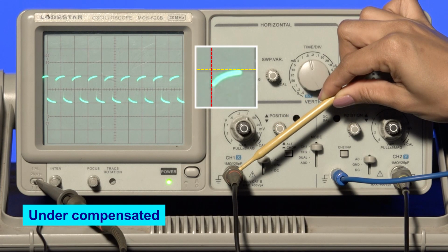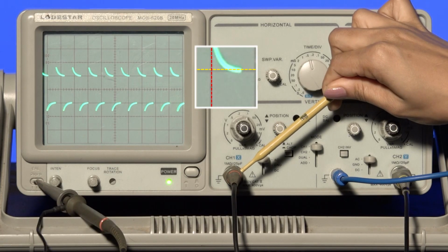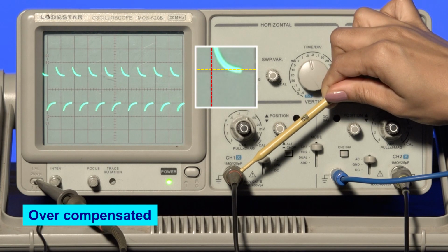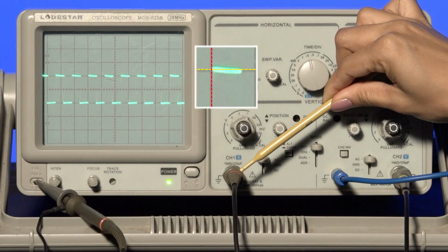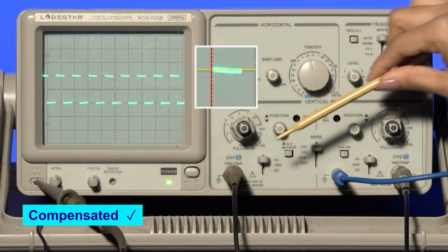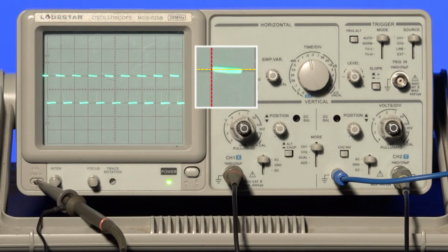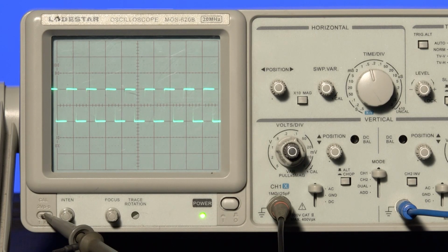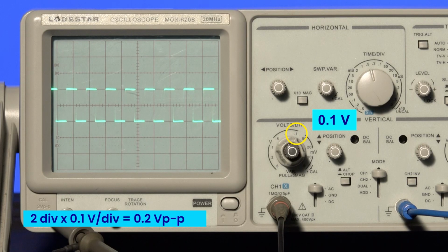Undercompensated, overcompensated, rightly compensated. If you look at the voltage level, you can note that the voltage reading is 10 times lower than the real value. That is due to the attenuation. Don't forget that during the experiment, we need to multiply the voltage reading by 10 times always.